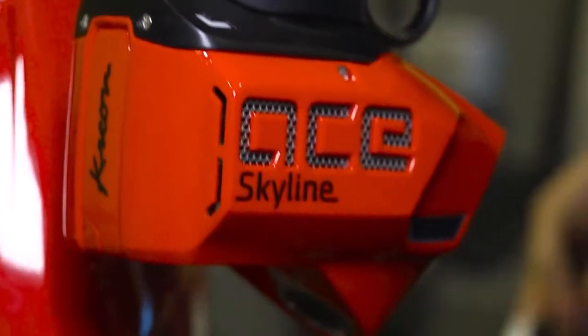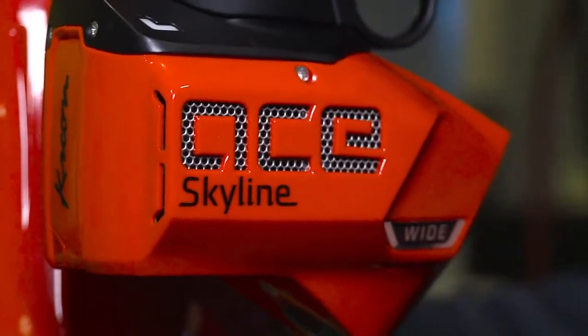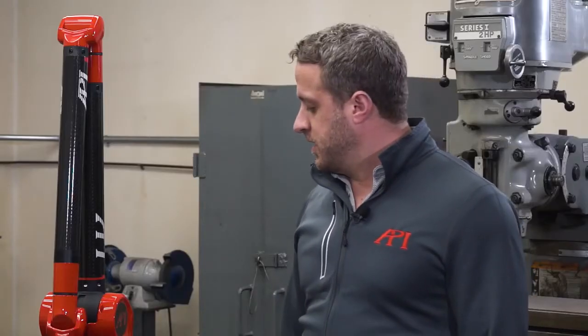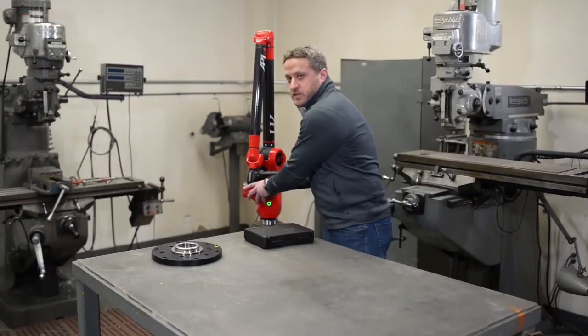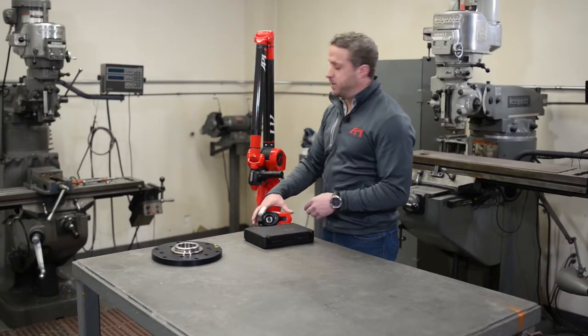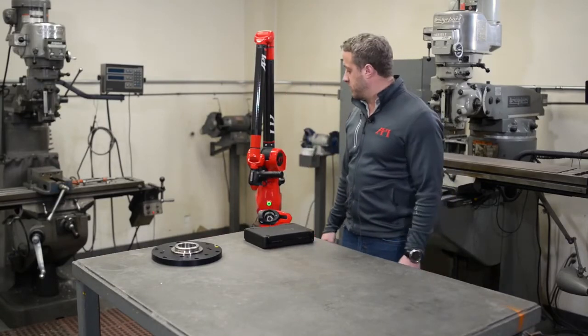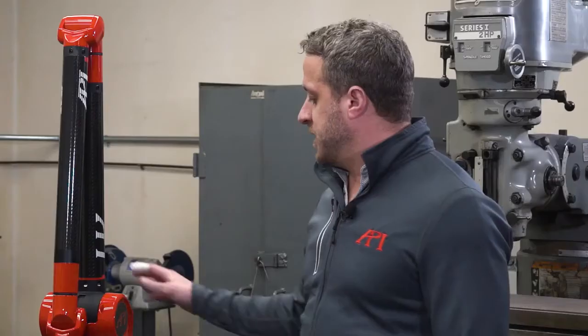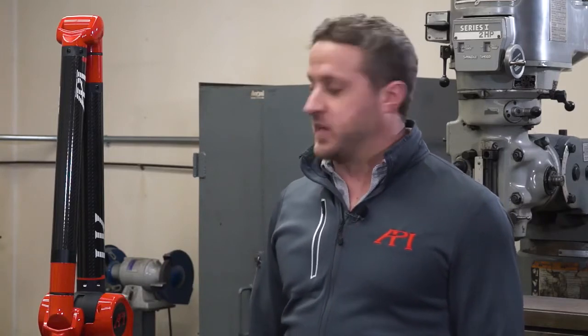The scanner that is on this is the Skyline scanner. It measures 600,000 points a second. And the accuracy is right around 48 microns. This also can be removed to include a probe on the end, where your accuracies will become better than the scanner. So initially, when it's just a probing arm, the accuracy single point repeatability is 27 microns, or just over plus or minus 1,000ths of an inch. When you add the scanner onto it, you're getting about 48 microns, or just under plus or minus 2,000ths of an inch. So definitely very accurate.